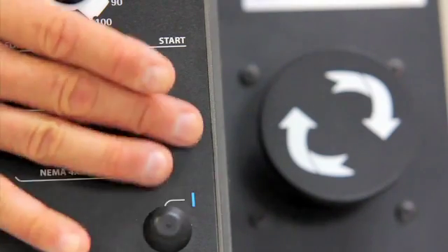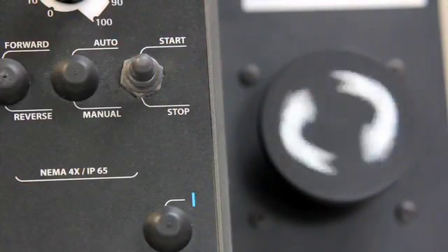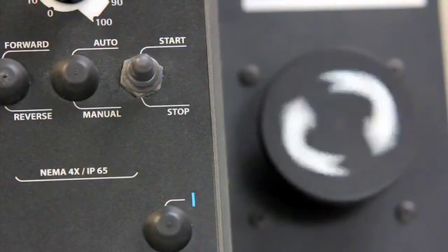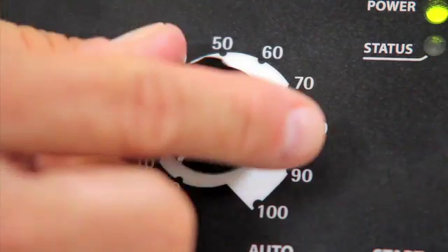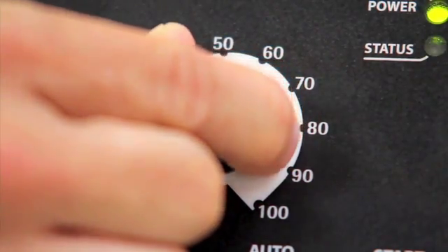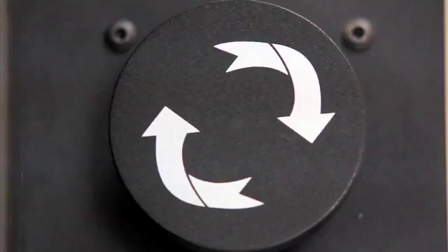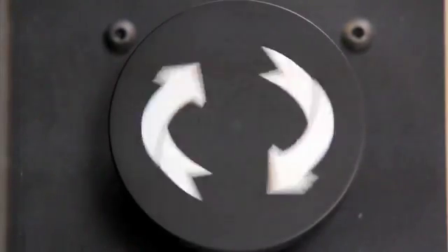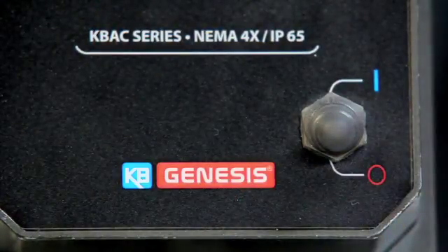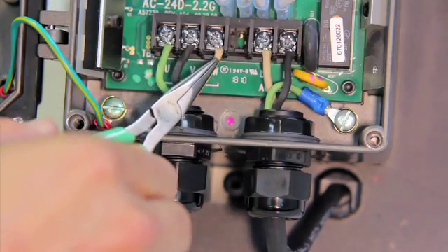Push the start-stop switch and release. The status light will start blinking green. Begin to increase the speed of the motor by turning the main speed pot clockwise. Check the motor shaft and make sure it is rotating in the correct direction. If it is not, power off the drive and reverse any of the two U, V, or W lines.